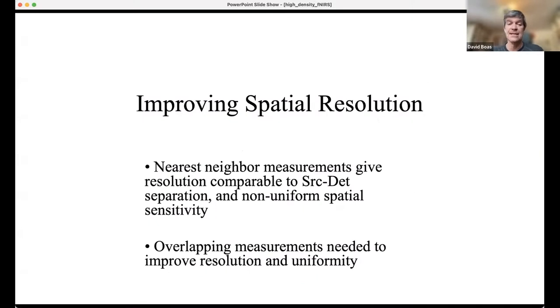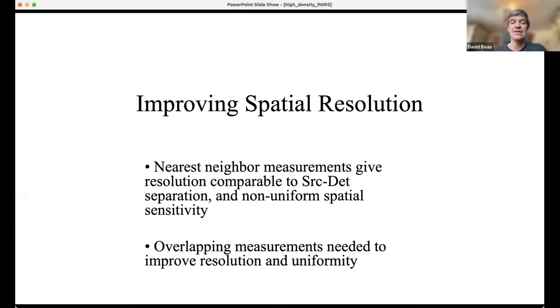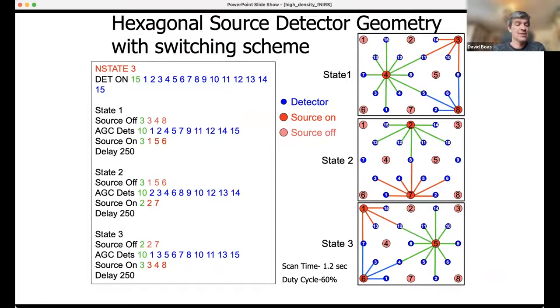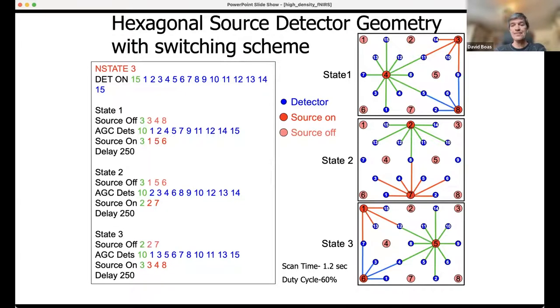So why do we want high-density measurements? High-density allows overlapping measurements, where every point in the brain is measured by multiple source-detector pairs. Through image reconstruction, this improves spatial resolution and spatial uniformity. The literature shows you can improve spatial resolution by a factor of two or better: with a 30mm source-detector separation, low-density gives ~30mm resolution, but overlapping measurements push that to 15mm or even 10mm in adult cortex close to the skull.